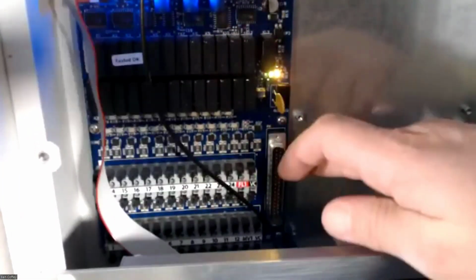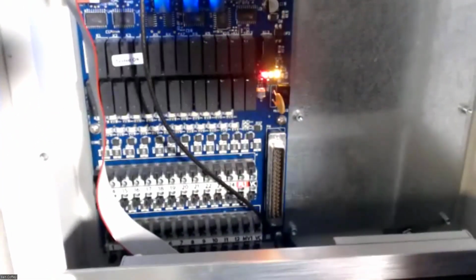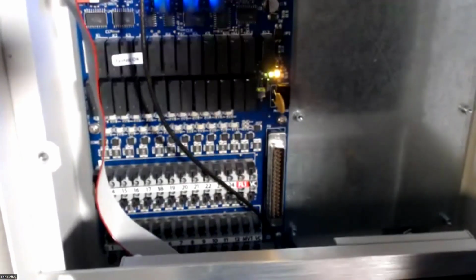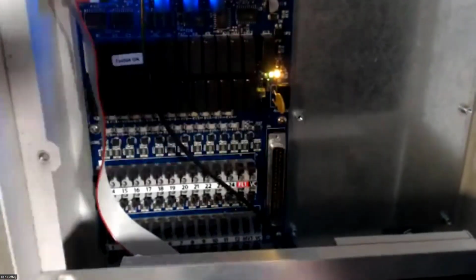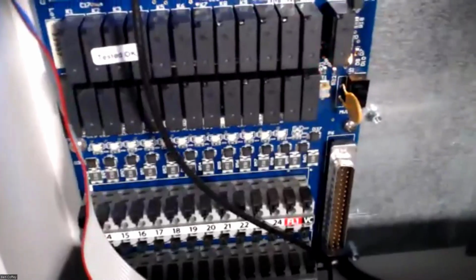This is where we plug in all of our valve wires. At the end of the valve wires, we see black VC and a red FL1. Jonathan, what is that? Your red FL1 is for your flow sensor, your first flow sensor in this case, POC1 positive. The black VC right next to it is your ground or negative for the flow sensor. So positive and negative for flow common sensor in the irrigation world. VC stands for valve common.